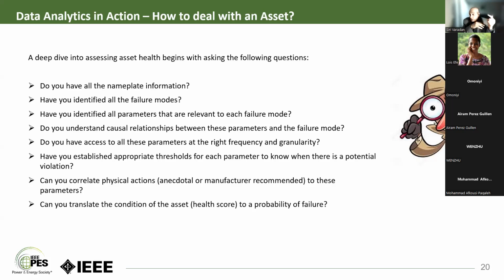You must know what is going on, and what parameters describe that failure. The question then becomes, are you getting all of these at the right frequency and the right granularity? Because sometimes events are quick, sometimes they're slow. For example, partial discharge is one of the things we typically measure on large high voltage transformers. Those are fairly quick events, especially once you start detecting a problem. Within 8 to 24 hours, there will be a failure.